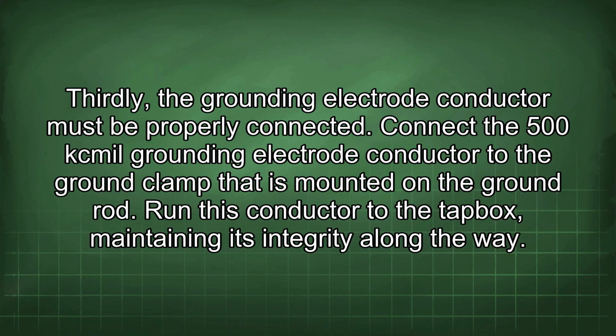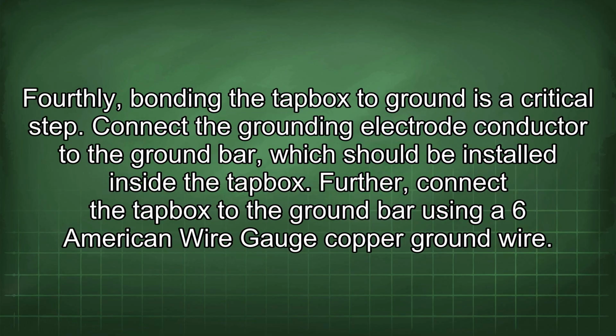Thirdly, the grounding electrode conductor must be properly connected. Connect the 500 kcmil grounding electrode conductor to the ground clamp that is mounted on the ground rod. Run this conductor to the tap box, maintaining its integrity along the way. Fourthly, bonding the tap box to ground is a critical step. Connect the grounding electrode conductor to the ground bar, which should be installed inside the tap box. Further, connect the tap box to the ground bar using a 6 American wire gauge copper ground wire.